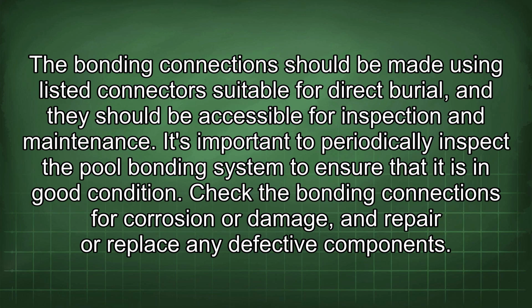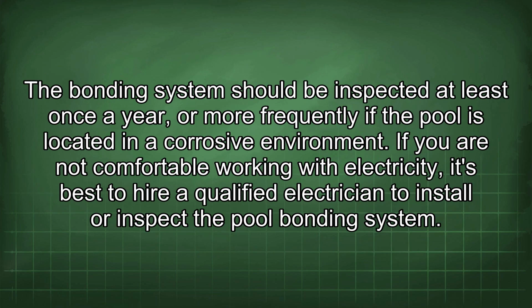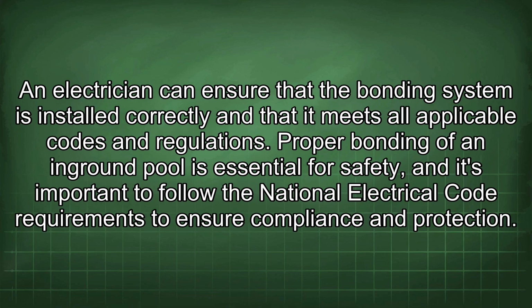It's important to periodically inspect the pool bonding system to ensure that it is in good condition. Check the bonding connections for corrosion or damage, and repair or replace any defective component. The bonding system should be inspected at least once a year, or more frequently if the pool is located in a corrosive environment. If you are not comfortable working with electricity, it's best to hire a qualified electrician to install or inspect the pool bonding system. An electrician can ensure that the bonding system is installed correctly and that it meets all applicable codes and regulations.